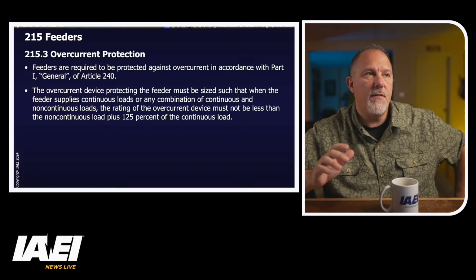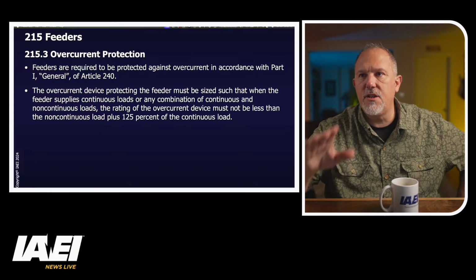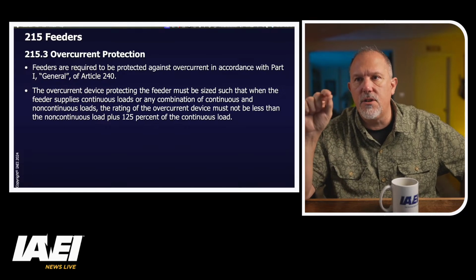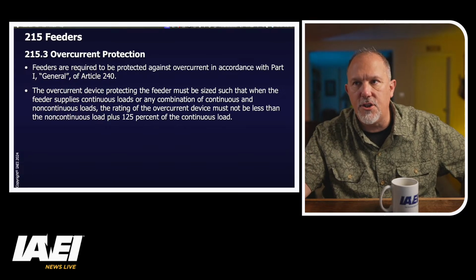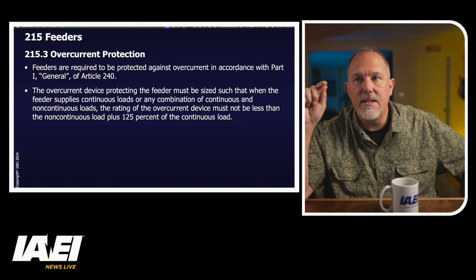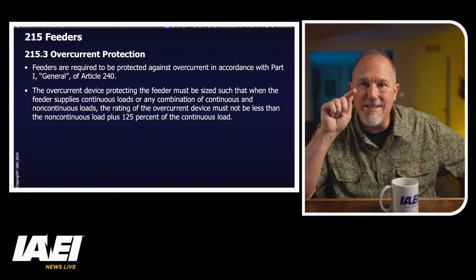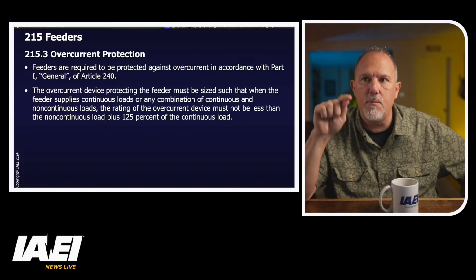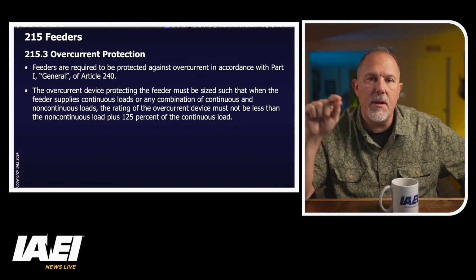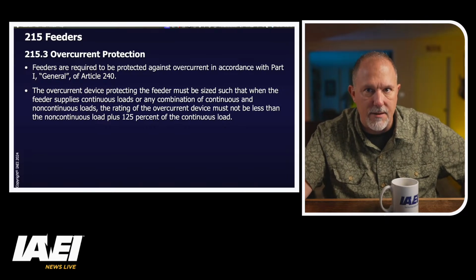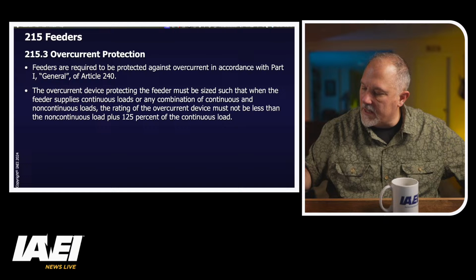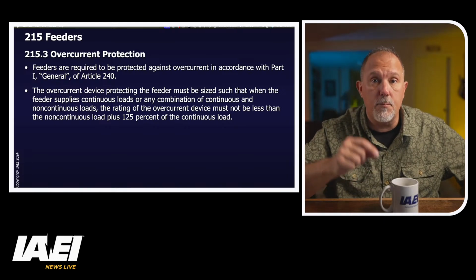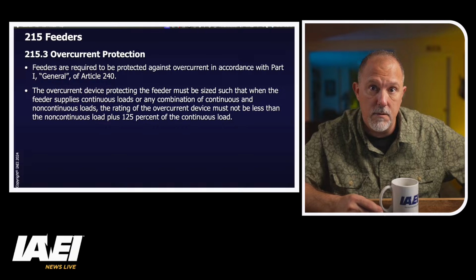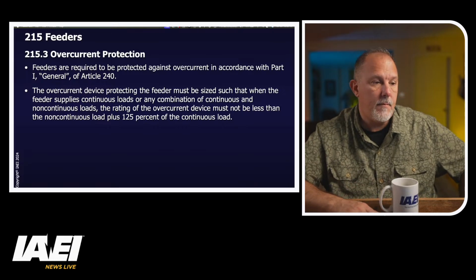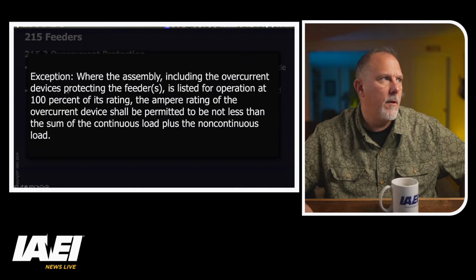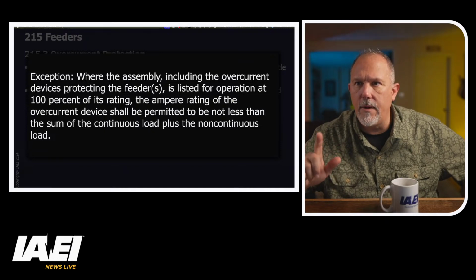So it says the overcurrent device must be sized for the feeder such that when the feeder supplies continuous loads or any combination. So what this is telling you is that your overcurrent protective device, unless it is rated for 100%, you have to multiply the continuous loads by 125%. And that's not a condition of the conductor, that's a condition of the overcurrent protective device itself. Okay? There's your exception for 100% rated equipment.